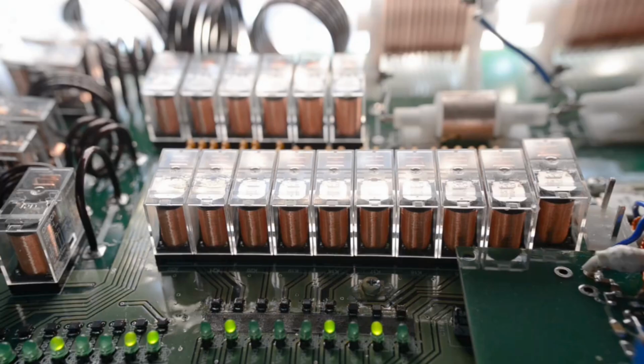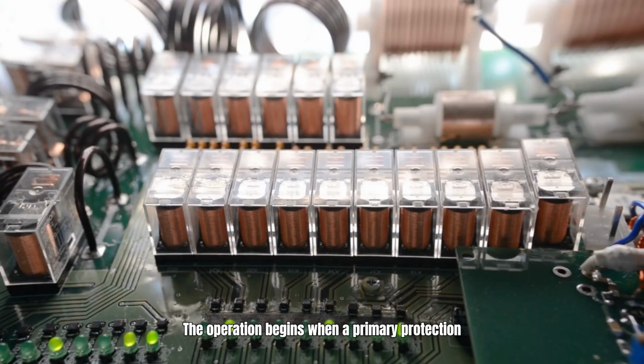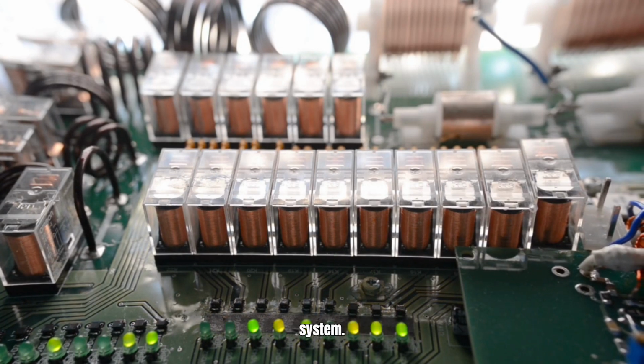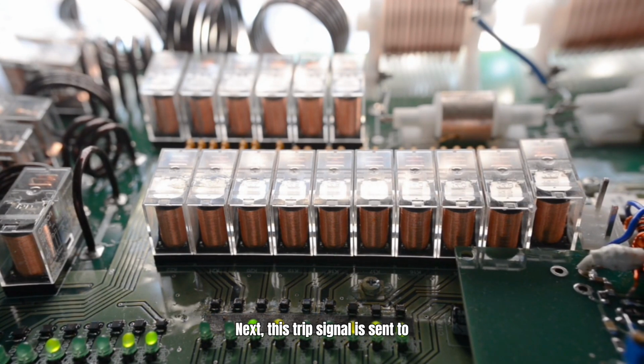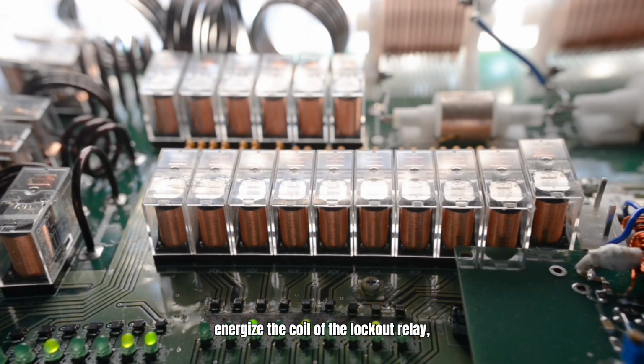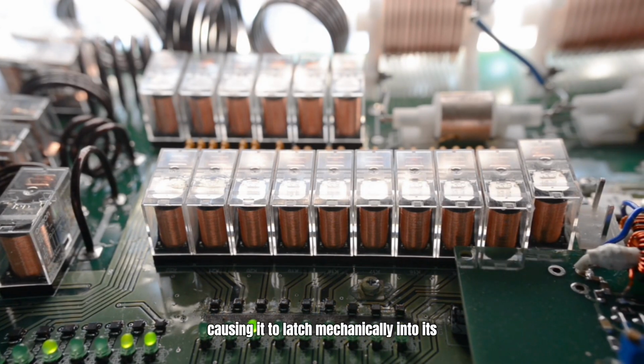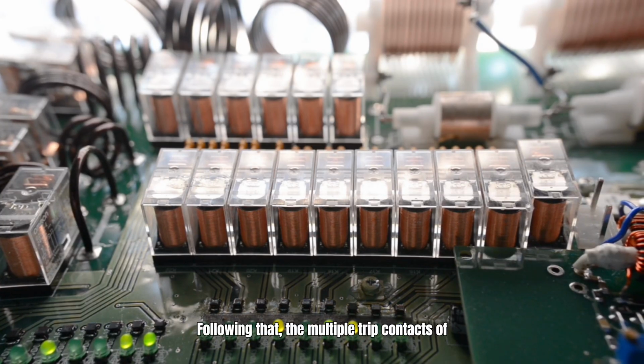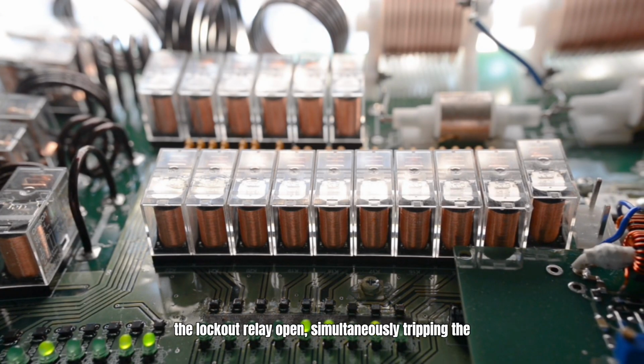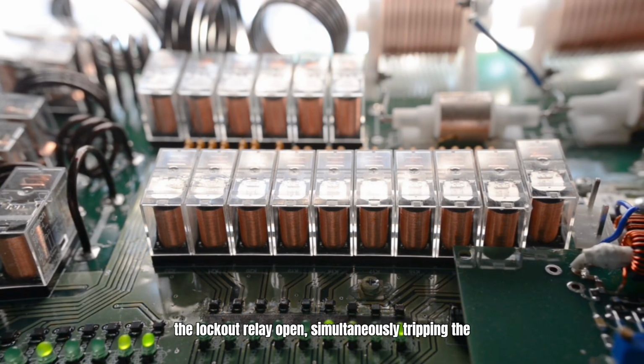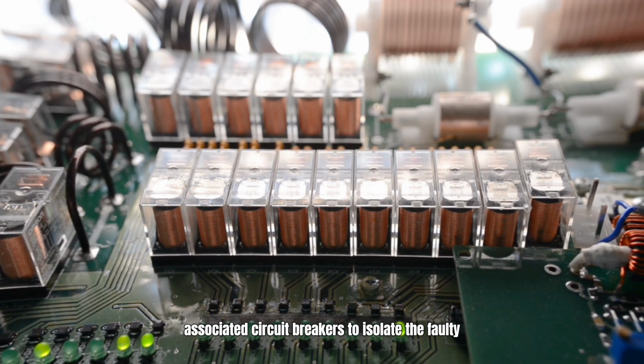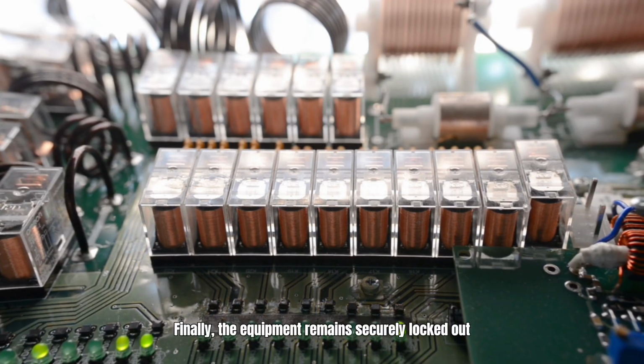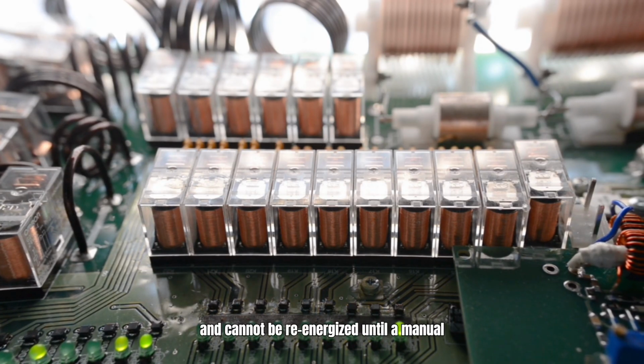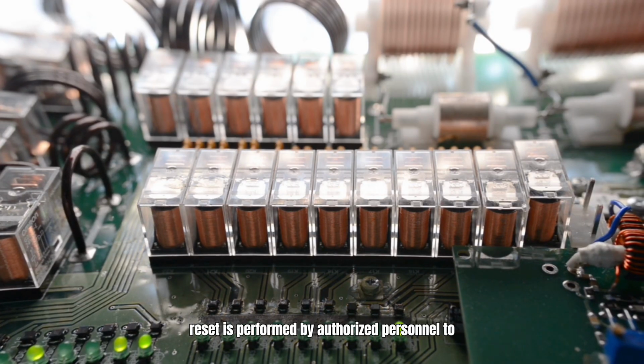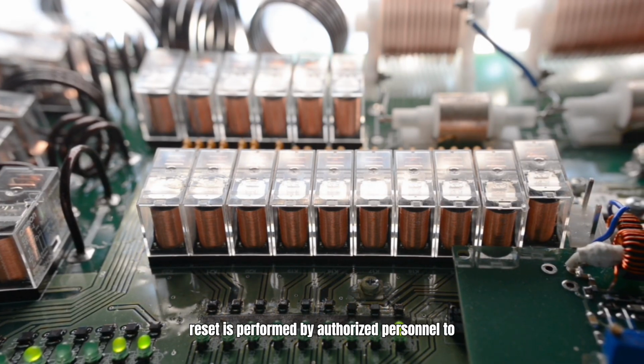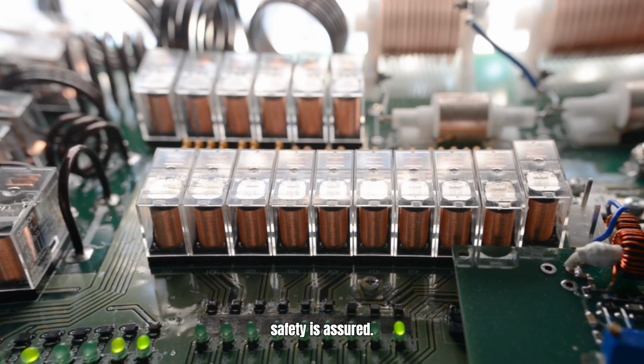The operation begins when a primary protection relay detects a severe fault in the system. Next, this trip signal is sent to energize the coil of the lockout relay, causing it to latch mechanically into its operated position. Following that, the multiple trip contacts of the lockout relay open, simultaneously tripping the associated circuit breakers to isolate the faulty section. Finally, the equipment remains securely locked out and cannot be re-energized until a manual reset is performed by authorized personnel to confirm the fault has been cleared and safety is assured.